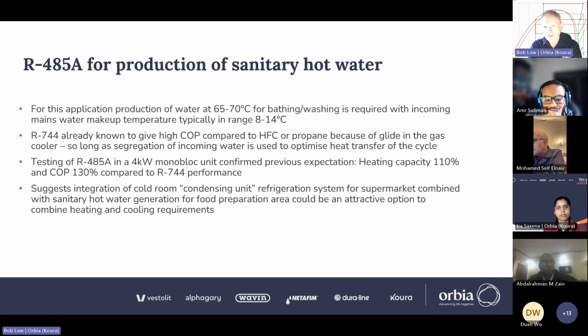refrigeration context. If you consider making sanitary hot water, domestic hot water is the other term often used, DHW, that needs to be 65 to 70 C, maybe even 75 C for bathing and washing, food preparation. If you're making up water, and the water typically would be between 8 and 14 C out of the tap, then a CO2 heat pump is more efficient than any fluorocarbon or even propane heat pump for that specific application if you get the technology design right, because you can glide match in the gas cooler. And that means you can get a much better overall COP than if you're condensing at a few degrees above the exit temperature of the water.